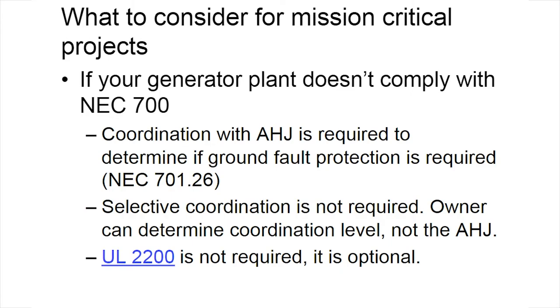It's a matter of preference; some people simplify and eliminate components. Sometimes the idea in mission critical is to have just the bare minimum. If it's not required, don't provide it. That creates issues: if you get a ground fault, you might trip a breaker upstream when you don't want to, but you control that issue by having pretty much all three phase loads, and procedures and other ways to take care of that. It's also important to say that if you're doing mission critical jobs, you don't need to have UL 2200 on your engines. That's optional. You can have it, but you don't need to. It's just nice to have.